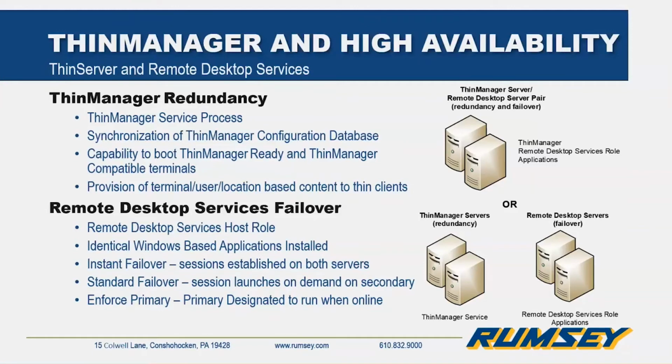And the 2 options there, I already kind of mentioned them, but we'll go over them here. Standard failover, and in standard failover, you have 2 servers configured. The primary is running. If the primary should fail, then the secondary would then spin up those sessions and serve them up, and then ThinManager would offer them up to the clients. So in a standard failover scenario, there will be a delay. There will be maybe a slight interruption of content delivery. So whatever length of time, whether it be seconds or even minutes, that it takes for those sessions to spin back up on the secondary remote desktop server, during that time frame, you won't have access to the content in ThinManager.